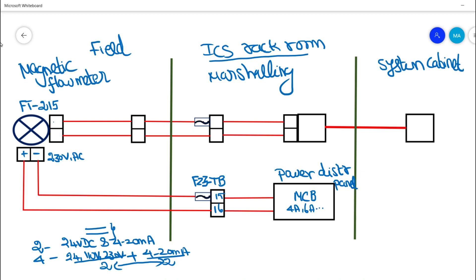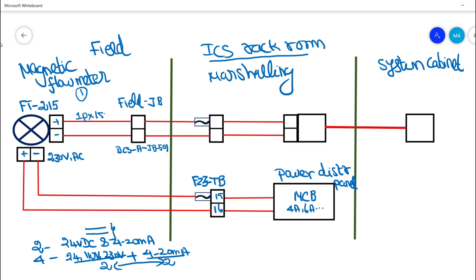The magnetic flow meter then gives a 4-20 milliamps output. It has a separate terminal for power supply and a separate terminal for the 4-20 milliamps analog output. This 4-20 milliamps analog output goes into a nearby field junction box — I'll name it JB-501, referring to analog input. In the field junction box we would get loops from multiple 4-wire instruments. In this example I've taken a single magnetic flow meter, but normally a field junction box would have more — perhaps 5 or even 10 magnetic flow meters. The cable used is a single pair, 1.5 mm² cable.